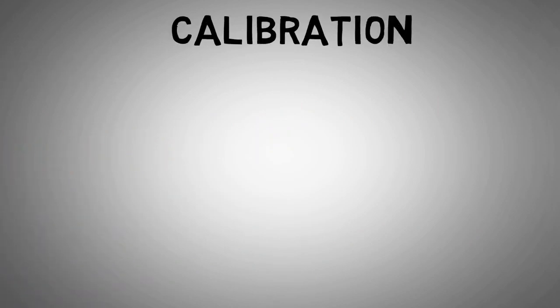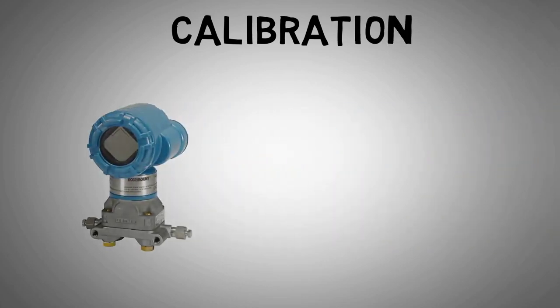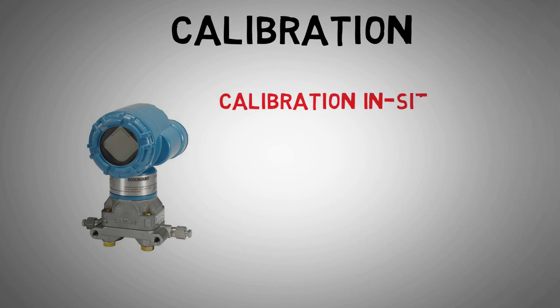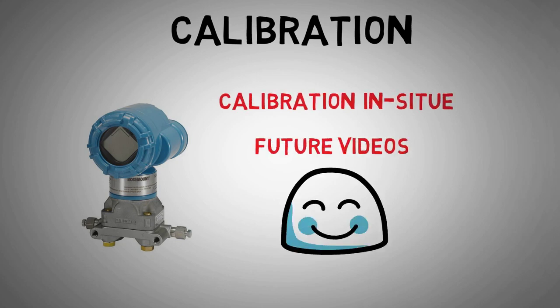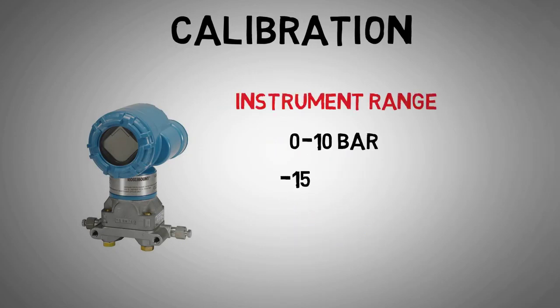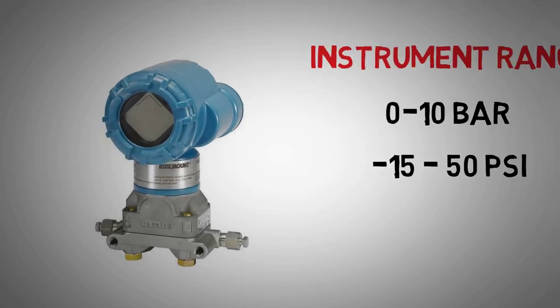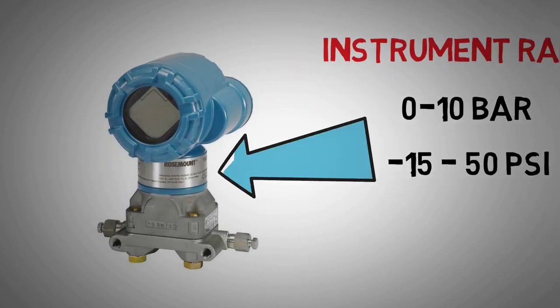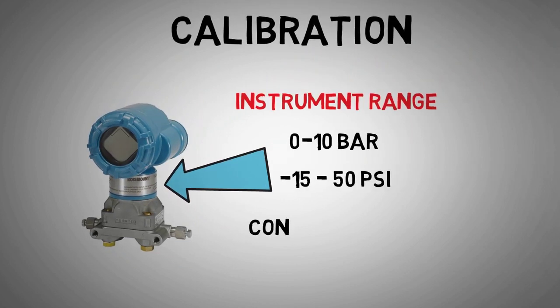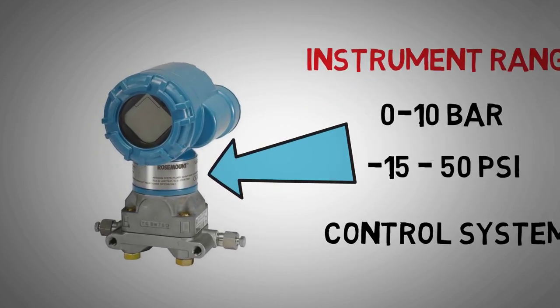We are going to assume the transmitter has already been removed and is in the workshop ready to be calibrated. Calibration is often performed in situ, but that's something we'll discuss in a follow-up video. We would first need to know the range of the instrument so that we know what test equipment to select and to calculate our test points. The range might be printed on data labels on the instrument, or we could look at the control system block we are connected to in order to find the range.